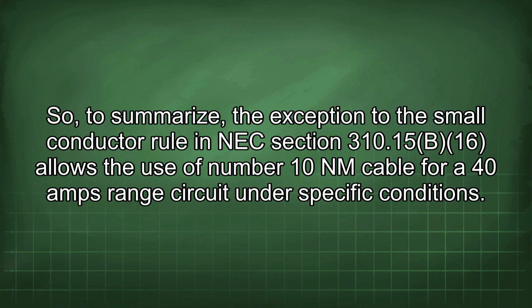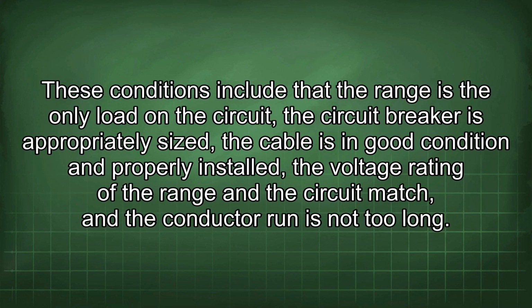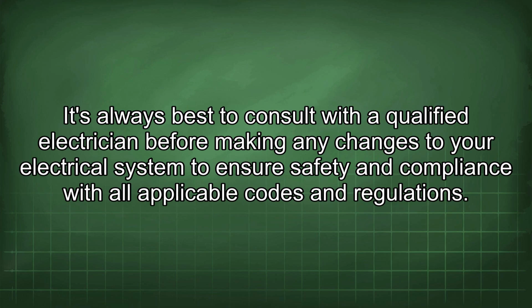So, to summarize, the exception to the small conductor rule in NEC section 310.15(B)(16) allows the use of number 10 NM cable for a 40 amp range circuit under specific conditions. These conditions include that the range is the only load on the circuit, the breaker is appropriately sized, the cable is in good condition and properly installed, the voltage rating of the range and the circuit match, and the conductor run is not too long. It's always best to consult with a qualified electrician before making any changes to your electrical system to ensure safety and compliance with all applicable codes and regulations.